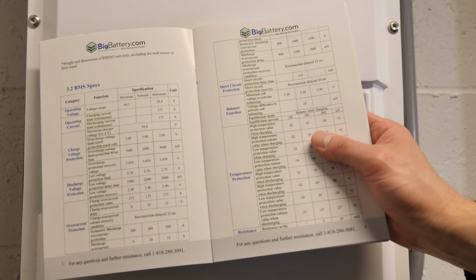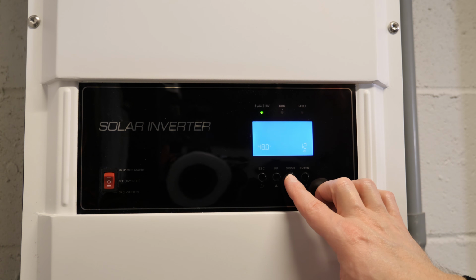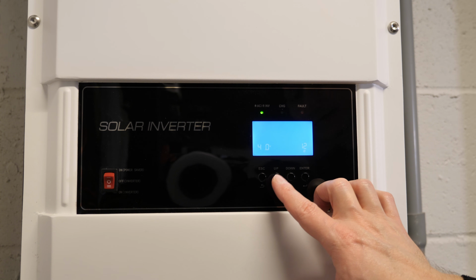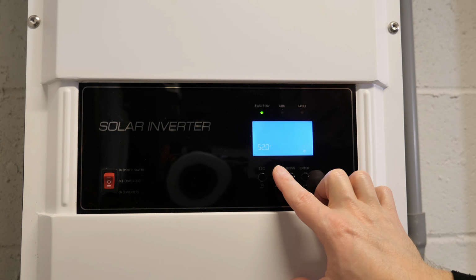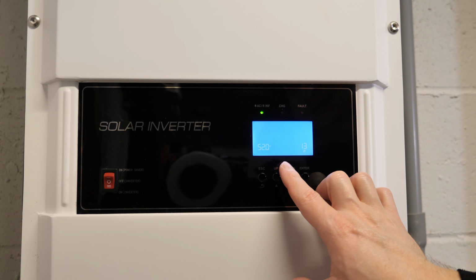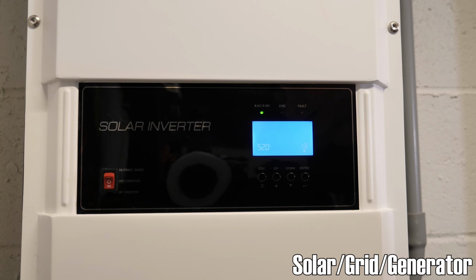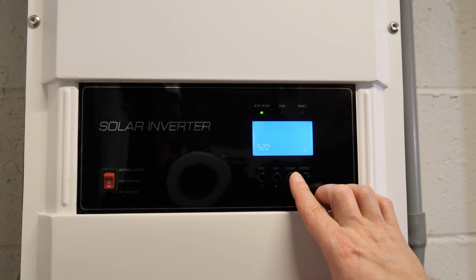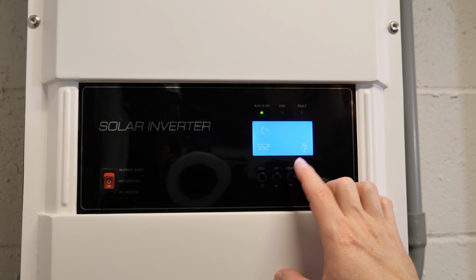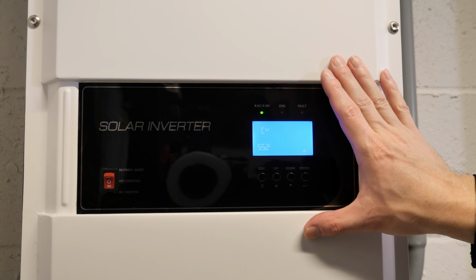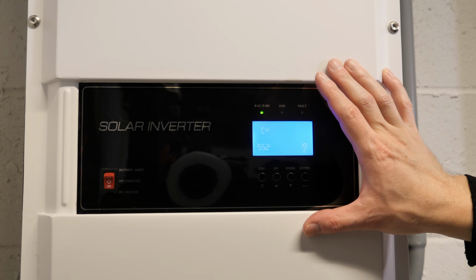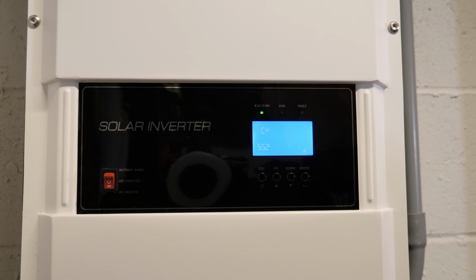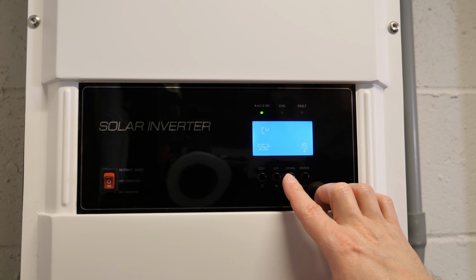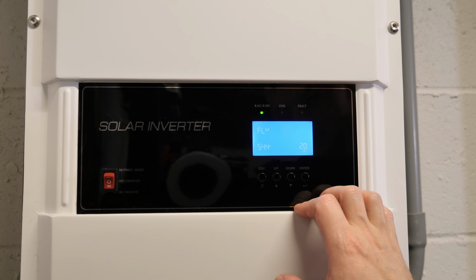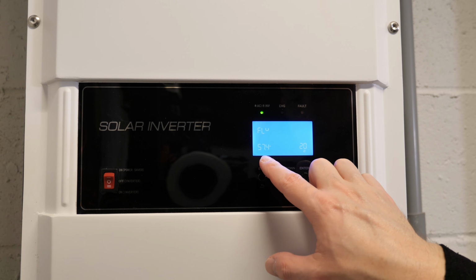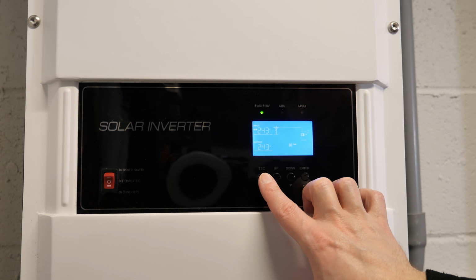I'm basically going to do that off of the spec sheet from Big Battery. Minimum on this battery, it says 44.3, so I might go to 46. Setting 13 for this inverter is whenever we want the inverter to go back on to battery—for example, if we were recharging the battery from grid. We're going to change this to 54 volts. Setting 19 for my inverter is your bulk charge. This inverter can only go up to 58.4. The maximum voltage of this battery is 58.8, so we're going to go up to 58.4. Float charge—lithium doesn't really technically need float charge, so we're just going to put it on 57.4. All right, and that is pretty much it.